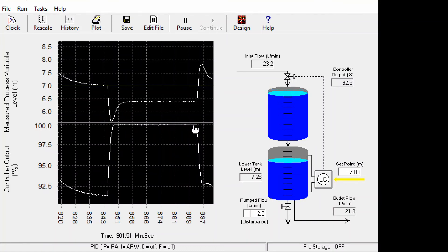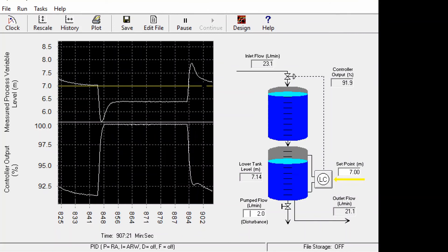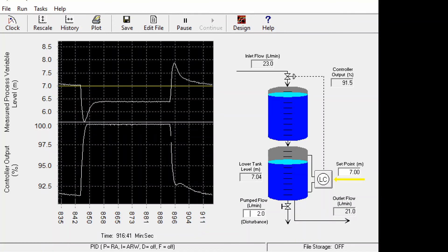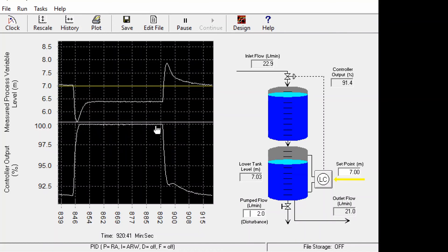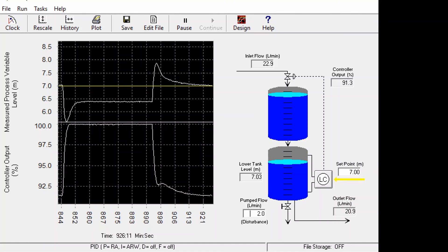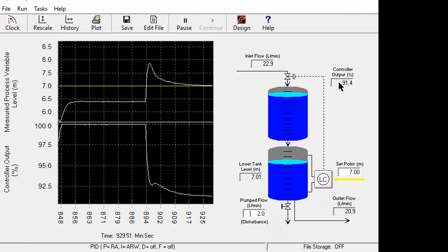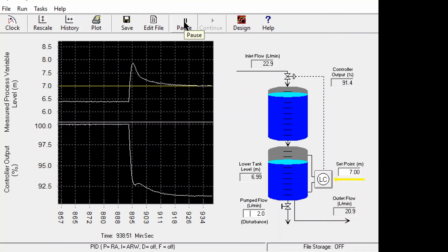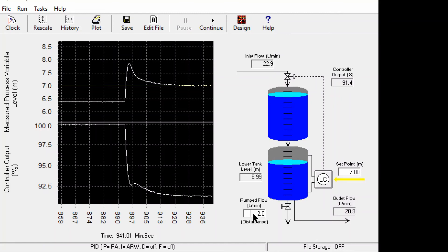The controller immediately takes action to bring the process to the desired value. This happened because the integral control was applied with anti-reset windup, meaning that when the controller saturated, the integral action was turned off. The maximum integral action was capped at 100%, so whenever the disturbance changed back to a value the controller could handle, the controller acted immediately and the process returned to the desired value quickly.